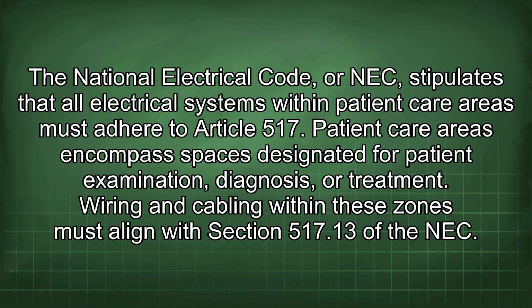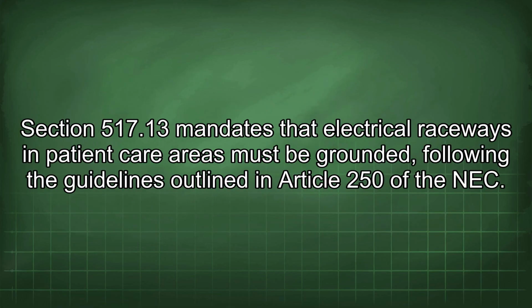The National Electrical Code, or NEC, stipulates that all electrical systems within patient care areas must adhere to Article 517. Patient care areas encompass spaces designated for patient examination, diagnosis, or treatment. Wiring and cabling within these zones must align with Section 517.13 of the NEC.